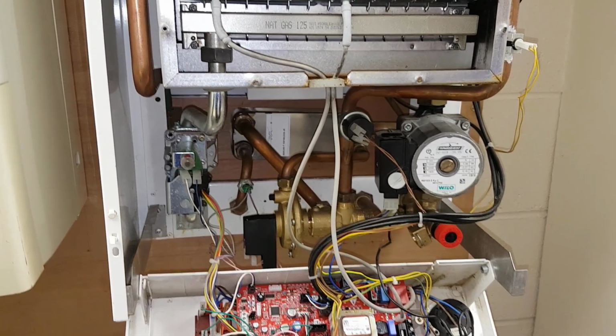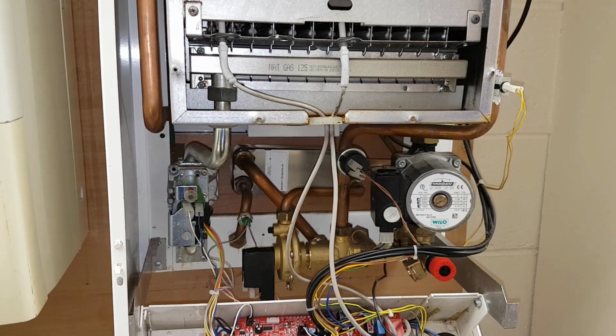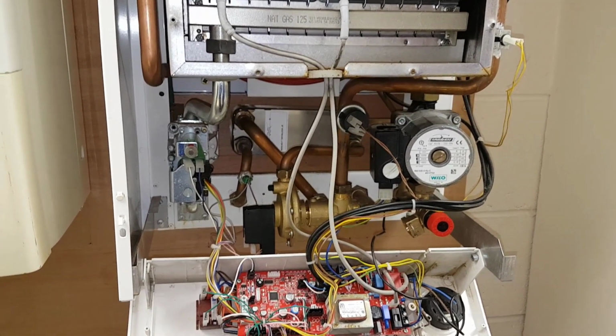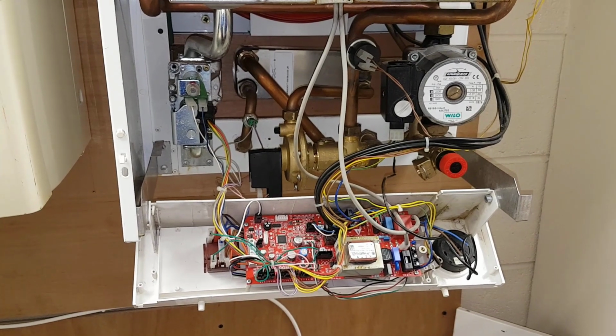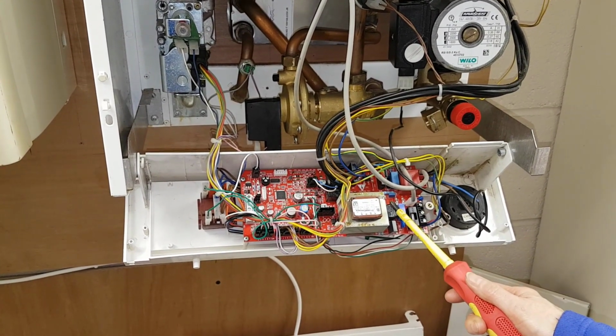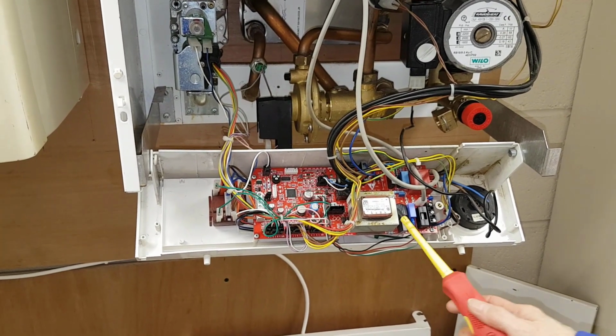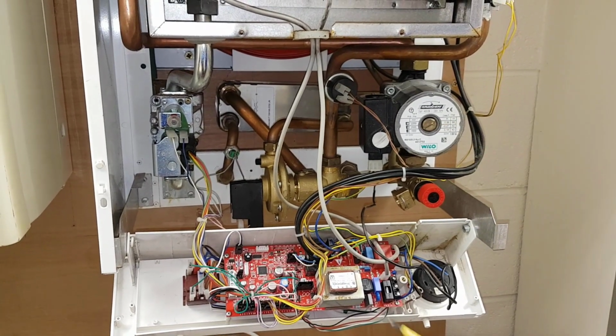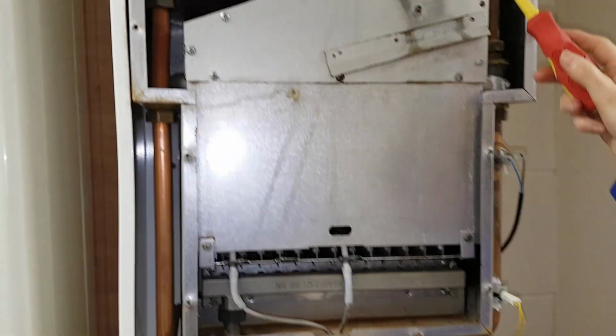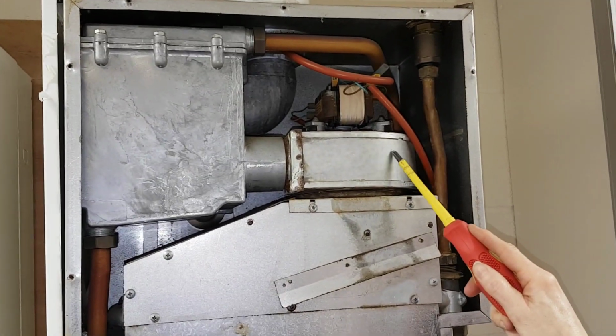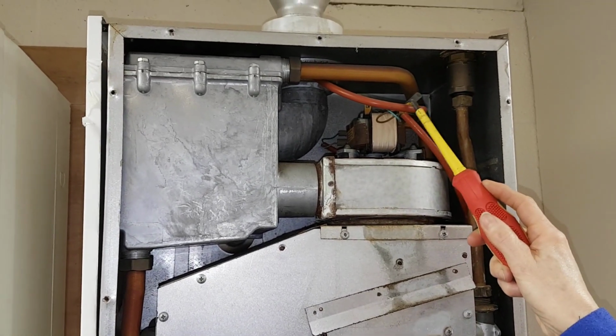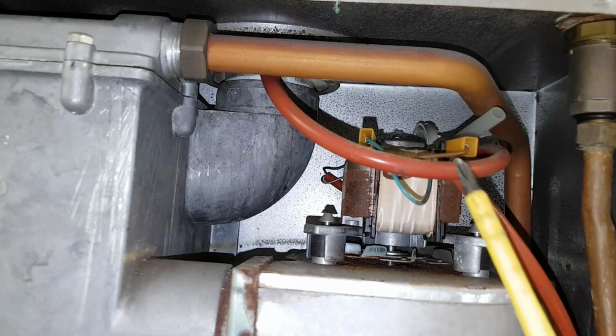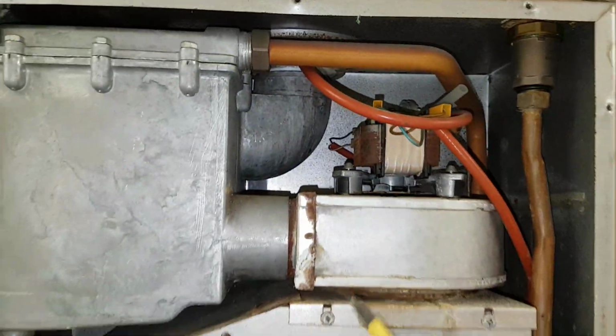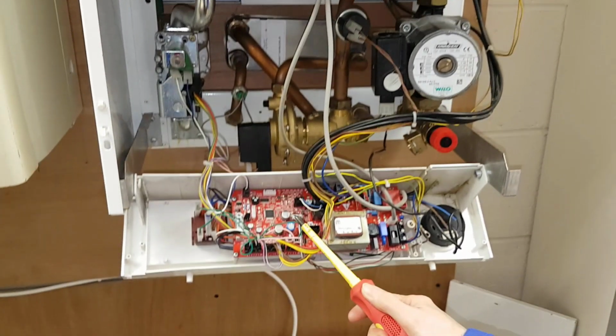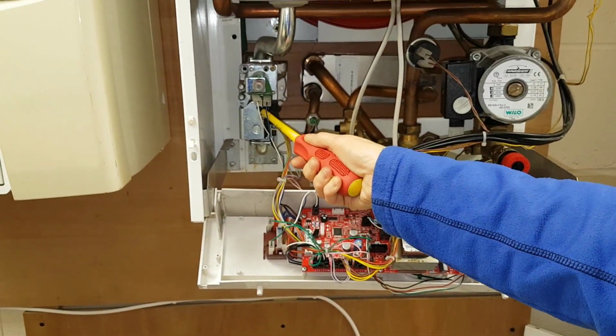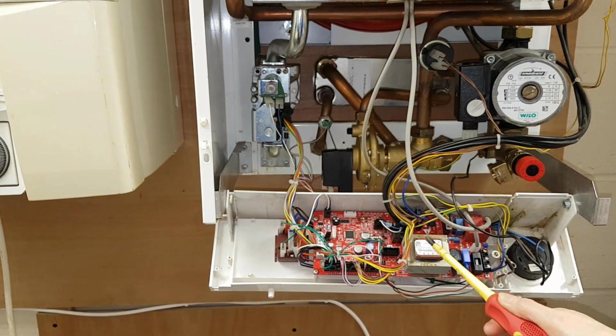Right, the customer is calling for heat in terms of the room thermostat and the programmer. So the external controls are calling for heat. That's picked up by the PCB, and the PCB then starts the pump running. The PCB then starts the fan running, and the fan running makes the air pressure switch. It goes back to the PCB, which then energises the gas valve. That comes back and it starts the ignition.